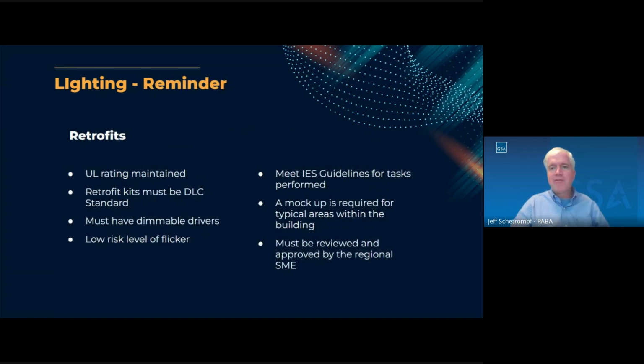So next up, we have an important reminder we wanted to throw out there on retrofitting of existing fixtures to LED. So first off, the final fixture shall maintain the UL rating. Retrofit kits must be DLC standard. We talked about DLC a couple slides back. The drivers shall be dimmable. You know, we've all seen retrofits where the outcome is brighter than we thought it was going to be. This helps guard us against that.